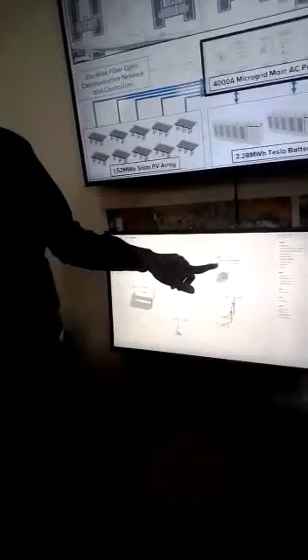This represents the communication panel physically. You've seen how vast the site is, how big it is physically. If there's a PV inverter on the last floor, on top of the roof, it's very far considering the scale of the site, so how do we communicate with it? Traditional communication won't work, so we have to use fiber optics. Fiber optic communicates with most of the assets that are far away and brings everything here. This panel is basically like a substation for the communication — everything is tracking, sending fiber optics to all the rooftops, all the car parks have fiber optics getting to them so we can effectively manage it.